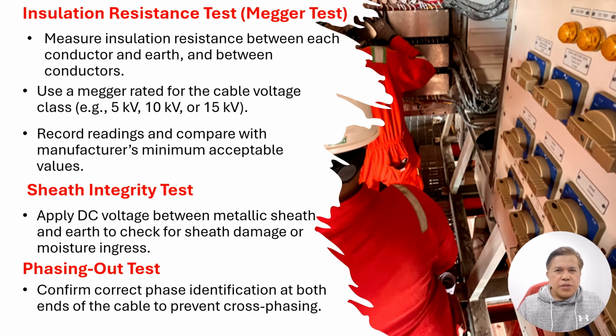And for confirmation during site acceptance testing, we do this check through instrumentation and also visually. You open all of the covers, check all the bus bar links and the bus bar installation, and also the cable, prior to handover to commissioning. So this is the whole process from quality inspections through installation, erection, and completion. All the ITR checklist test sheets have been done, then proceed to RFHU and ready for handover. So this is how we do the testing of high voltage cable.